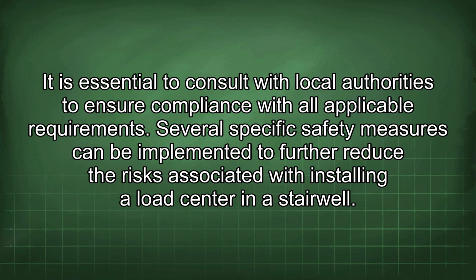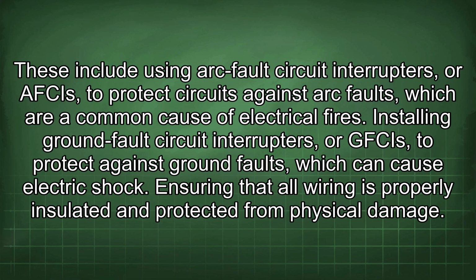Several specific safety measures can be implemented to further reduce the risks associated with installing a load center in a stairwell. These include using arc fault circuit interrupters, or AFCIs, to protect circuits against arc faults, which are a common cause of electrical fires. Installing ground fault circuit interrupters, or GFCIs, to protect against ground faults, which can cause electric shock.